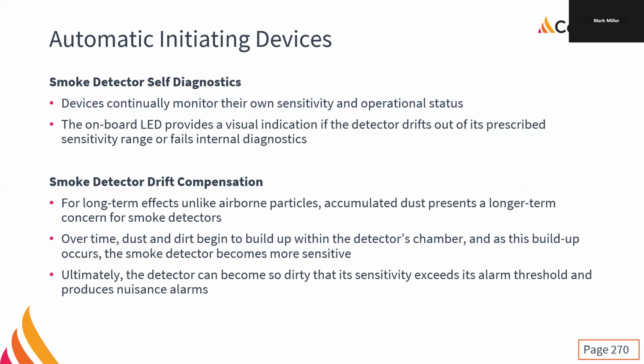If you put a little tiny computer in there, it's also now able to do some self-diagnostics. It can monitor its own sensitivity and operational status, and it can compensate for dirt. Right? The dust accumulation over the days and months and years that it's in use, it's able to tell that it's getting dirty and adjust its threshold over time. So we used to have a lot of issues where, as it got dirtier and dirtier, it became more and more sensitive, a lot more false alarms. That's less of an issue now, partly because of the baffle designs, but also because the drift compensation has gotten so good. But eventually, there's just going to be too much.